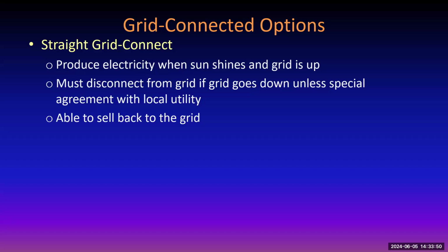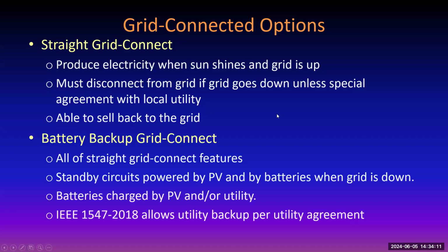And the rules are that if you have a straight grid connect inverter, and the grid goes down completely, it has to disconnect from the grid within 2 seconds. And I think they arrived at that number because no utility has ever been able to respond to an outage in less than 2 seconds. So anyway, that's our story on the grid connect. If we have a battery backup grid connect, which we're not going to go into today, it has all the features of straight grid connect, but also has standby circuits that can be powered by the solar and by the batteries when the grid is down. And the batteries can be charged either by the solar or by the utility or both, depending on who's available at the time.